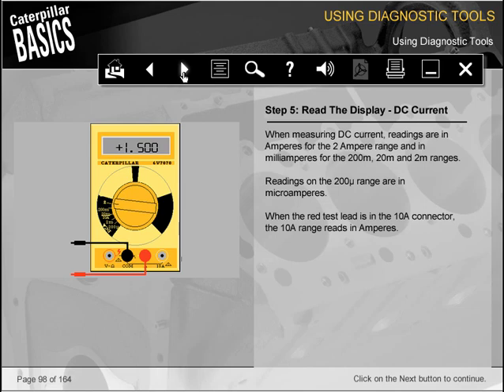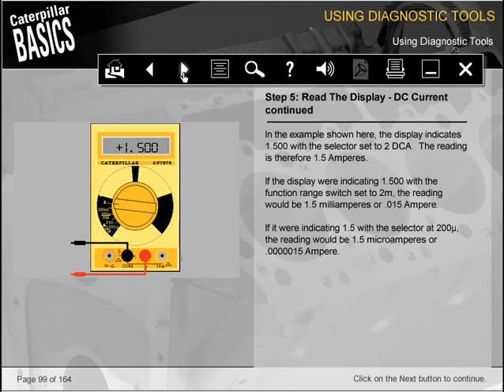When measuring DC current, readings are in amperes for the 2 ampere range and in milliamperes for the 200m, 20m, and 2m ranges. Readings on the 200 microsymbol range are in microamperes. When the red test lead is in the 10A connector, the 10A range reads in amperes. In the example shown here, the display indicates 1.500 with the selector set to 2 dCA. The reading is therefore 1.5 amperes.